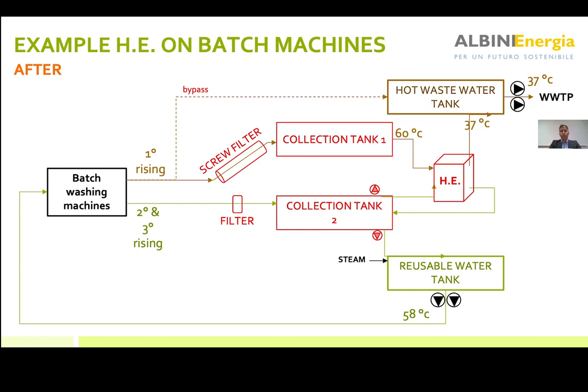We pumped it through the heat exchanger and raised the temperature up to 58 degrees, instead of the previous 36 to 38. On the other hand, we reduced the temperature of the first rinsing from 60 to 37 degrees. This is also pretty important to understand.